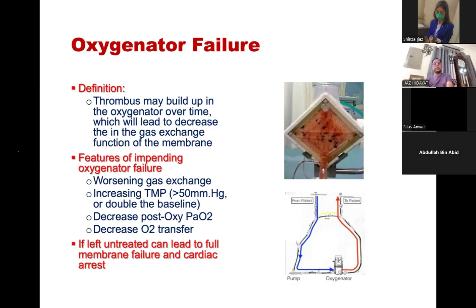For example, it depends on the flow and the TMP, and on the temperature. So if your gas transfer is decreasing, you can change the oxygenator by an elective method instead of in a disaster or an emergency situation. You can have an MDT meeting among the physicians, nurses, perfusionists, RT and the team members, and decide to change your oxygenator electively instead of in any emergency situation.